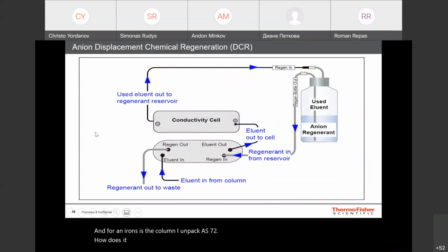How does it work in this DCR chemical regeneration mode? Eluent from the column enters the chemical suppressor to the eluent inlet port and goes out through the eluent out port. Then it flows through the conductivity cell, and finally it goes to the regenerant bottle. There is no special pump for delivering the regenerant of the suppressor. Practically, the eluent is pushing the liquid from the regenerant bottle to go out to the regenerant inlet of the suppressor, and coming out from the regenerant outlet, it goes to the waste.